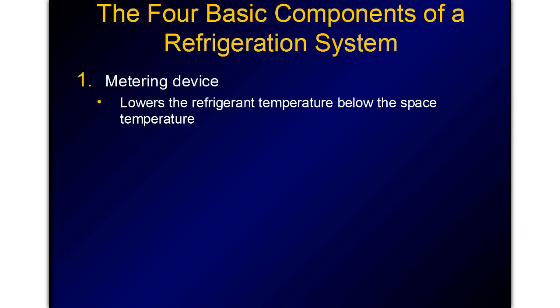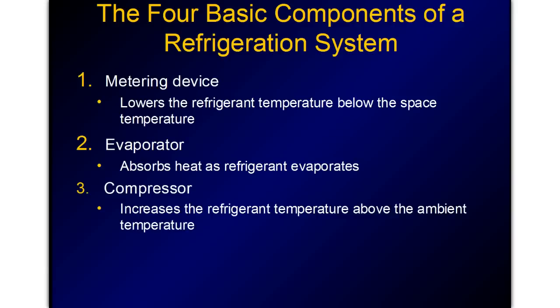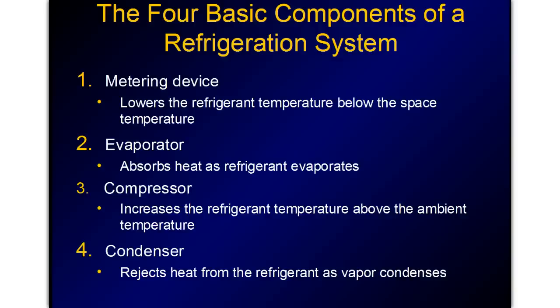The four basic components of a refrigeration system are the same as those of an air conditioning system. The metering device in a refrigeration system lowers the temperature and pressure of the refrigerant much lower than a residential air conditioning system. The evaporator does basically the same thing and absorbs heat, changing the state of the refrigerant and absorbing superheat. The compressor is a little different — they are designed to compress low-density vapor to higher pressures. The condensers are nearly identical; they just reject the heat from the refrigerant vapor and add a little sub-cooling before sending it back to the metering device. We'll learn about metering devices, evaporators, compressors, and condensers in the follow-on course.